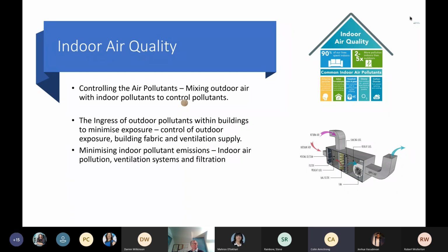Historically, there has been a lack of awareness amongst occupiers and buildings that certain activities pollute the indoor environment and can cause adverse health effects. A common misconception is that dilution with fresh air is the only way of removing harmful contaminants from the occupied space. It's more effective to control the source of the pollutant if possible, especially as outdoor air may itself be contaminated coming into the building.